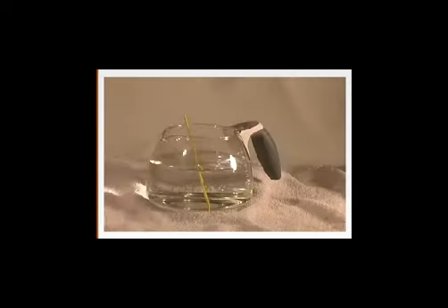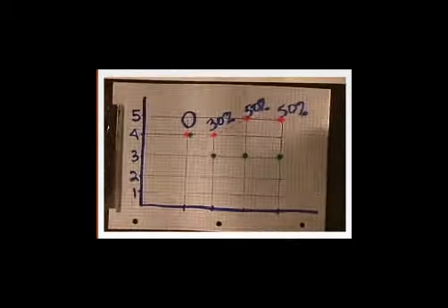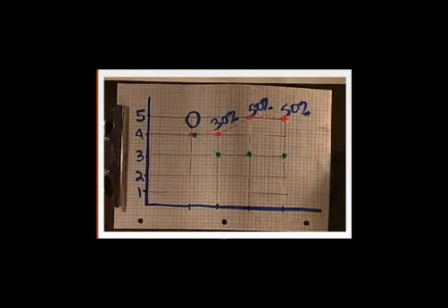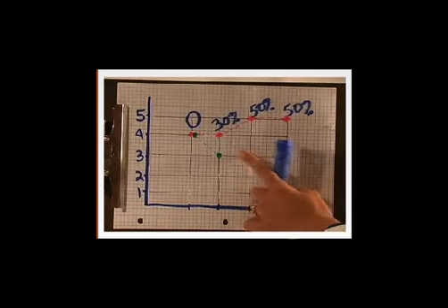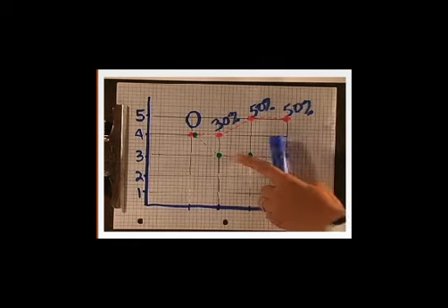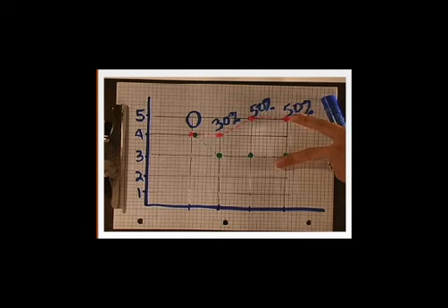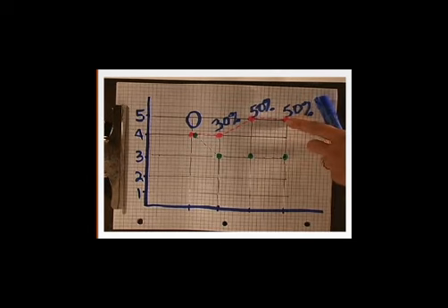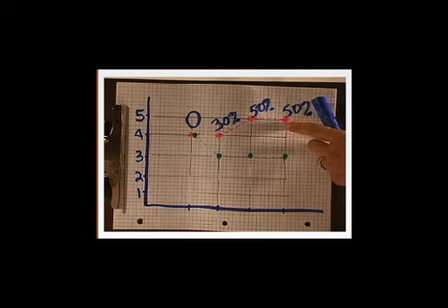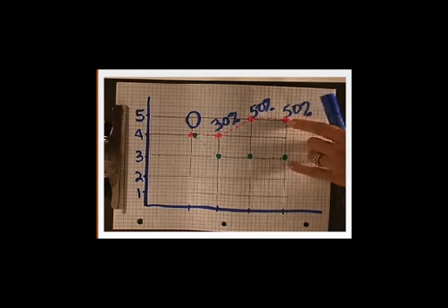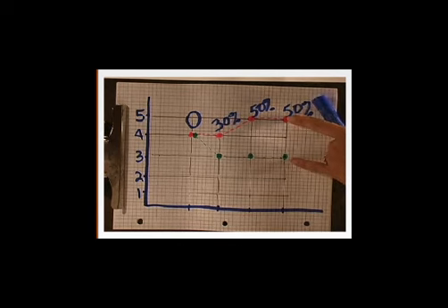Now we can use this data also to look at bias. So what happened here was a slowly increasing bias and then leveling out so that you see a consistent difference between the two. We had the one probe that was hotter, down near the bottom where the heating pad was, consistently biased high. So a bias is a consistent difference in one direction.